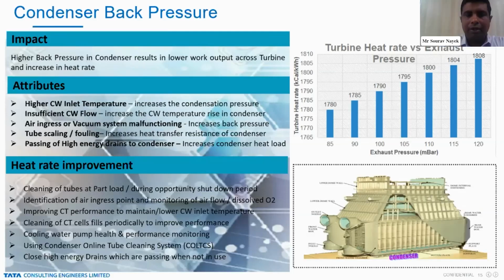Now, what are the measures for maintaining the condenser back pressure, which is a very key aspect? One, cleaning of the tubes at part load or during the shutdown period. We have to clean the condenser tubes so that the scaling and fouling effect is very nominal and within the acceptable limit. Air ingress point monitoring of the airflow is very important so that proper sealing is established and we can see that vacuum pulling is within our desired value.